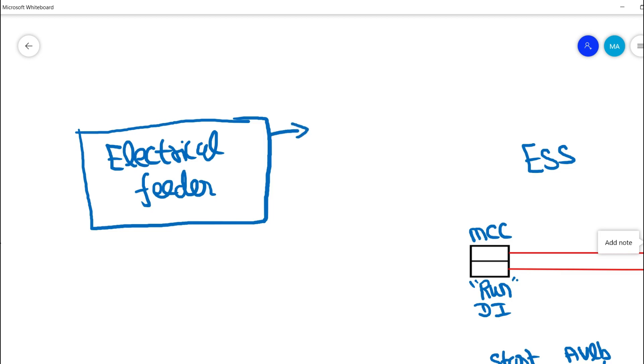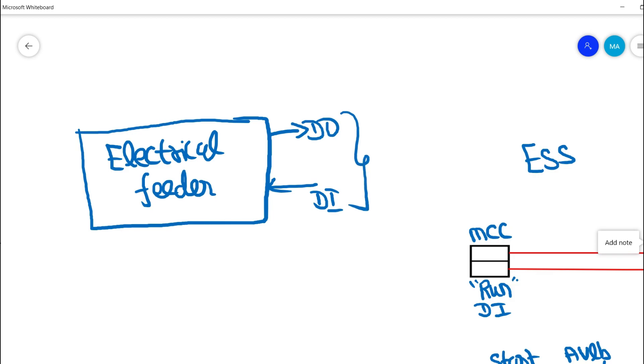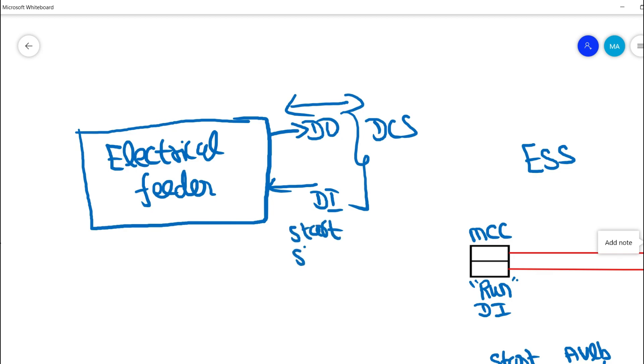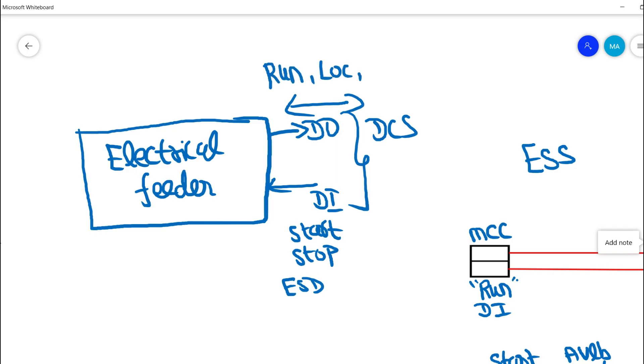In this electrical feeder we have digital outputs and digital inputs between DCS and the electrical feeder. Digital inputs from DCS to the electrical feeder include start command, stop command, and ESD trip — with ESD trip coming from the ESD panel. Digital outputs from the electrical feeder to DCS include run feedback, local/remote indication, and availability signals.